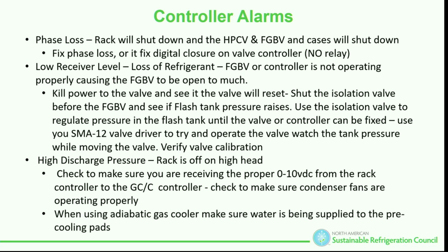How many times when I walk into an E2, a Danfoss, an 880, 880A, whatever, is the alarm that I'm interested in the top alarm? No. The alarm I'm seeing on the top, is that the one I'm interested in? I'm interested in the first one that occurred that day, or in that series. Because I may lose something on oil or on phase loss, and what's it going to trigger? Multiple other alarms. So if I'm trying to troubleshoot this one, that's not the root. I have to go back to the root cause, amen? Amen. So that's what we want to do.